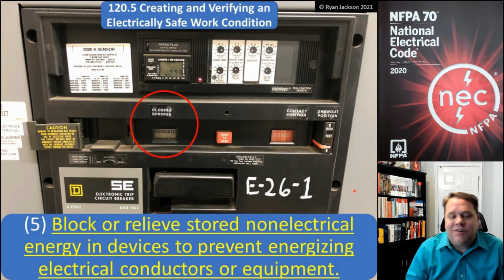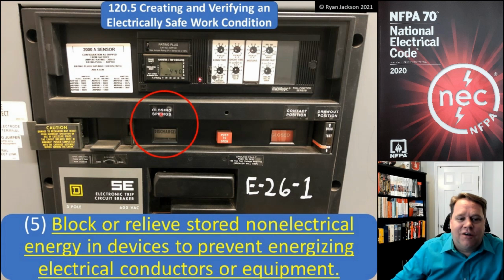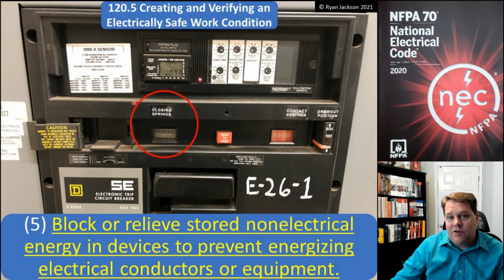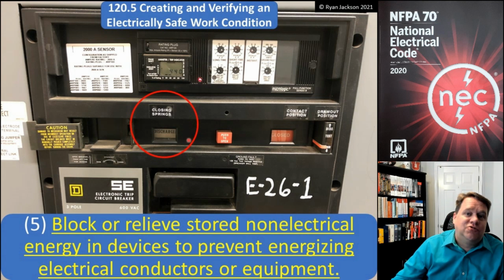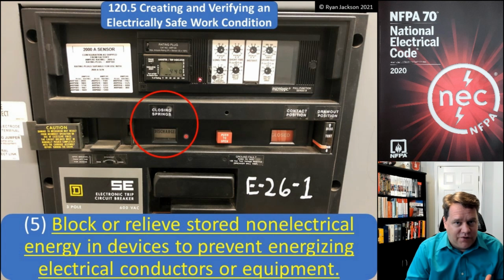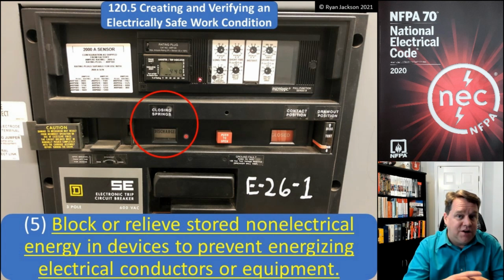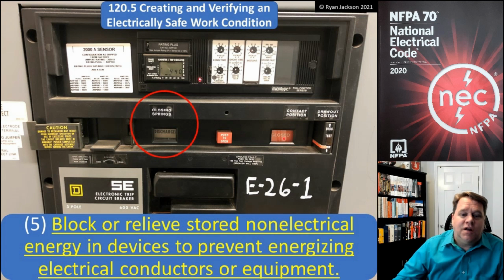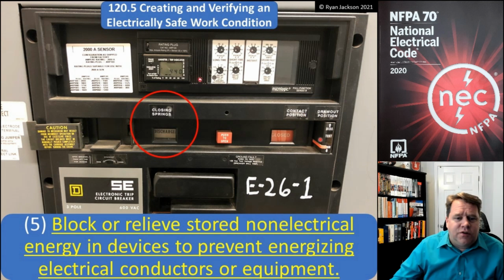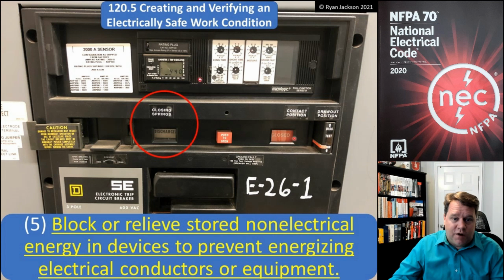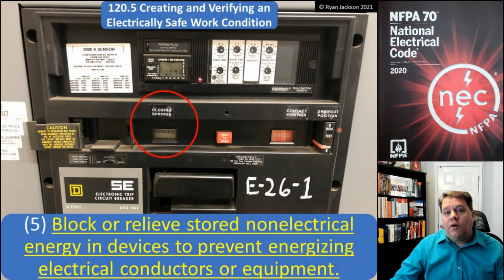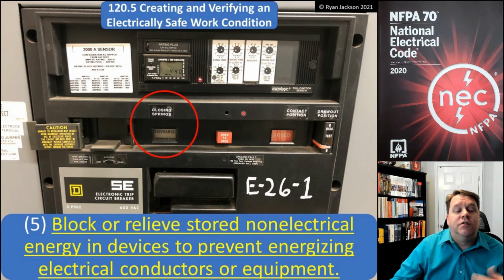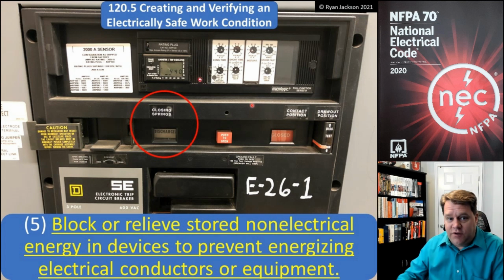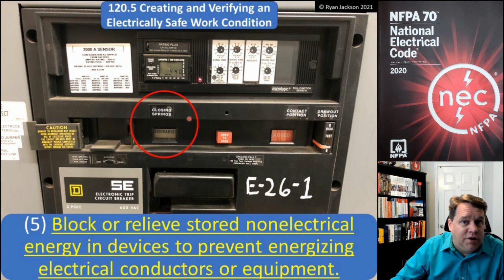Well, what is she doing when she's pumping that thing up? She's putting tension on the closing springs. When we're de-energizing equipment, we need to make sure that tension is off of the closing springs. If the springs are without tension, they're not going to close on us. So we need to shut everything off, figure out what to shut off, interrupt the load. We need to visually verify it if we can. We've got the draw-out position on here. We need to remove any stored electrical energy. And then number 5, we need to block or relieve any stored non-electrical energy that could energize the equipment. So we need to make sure that the closing springs are discharged.